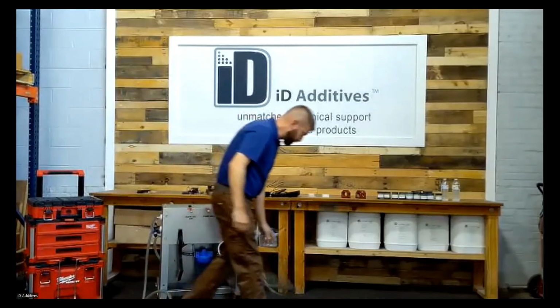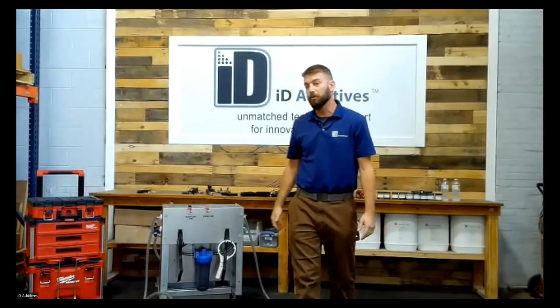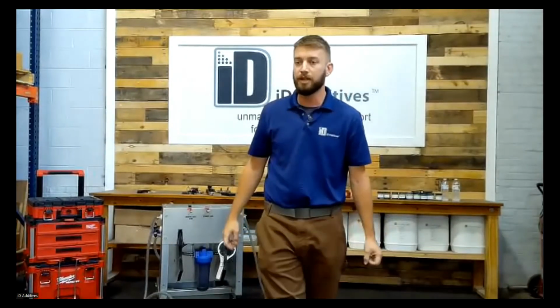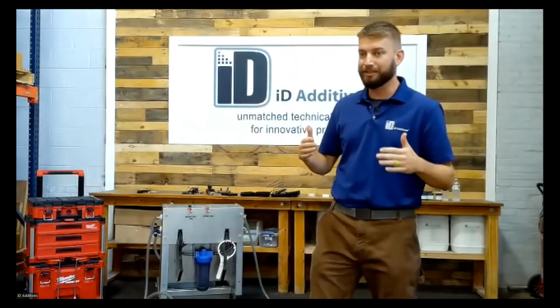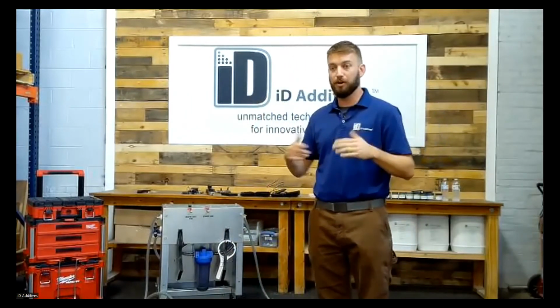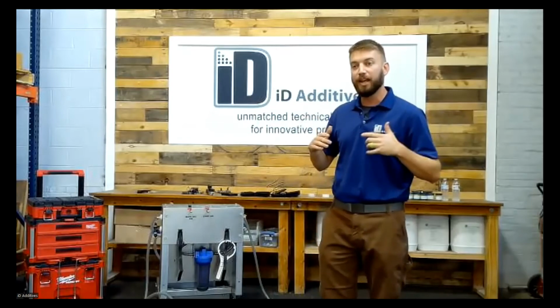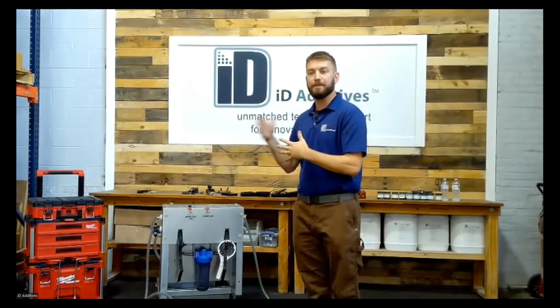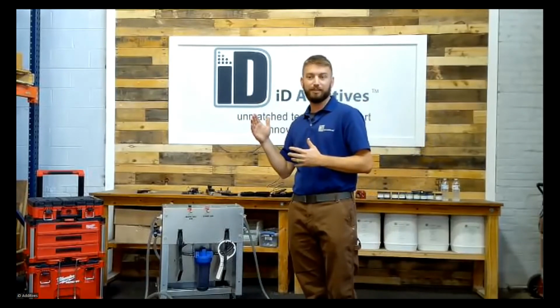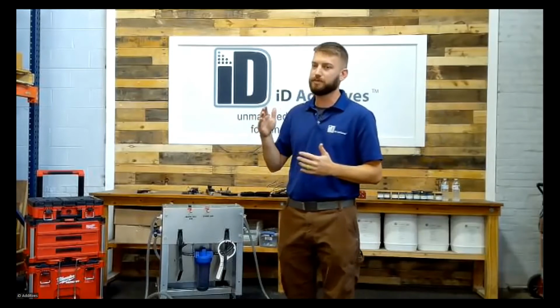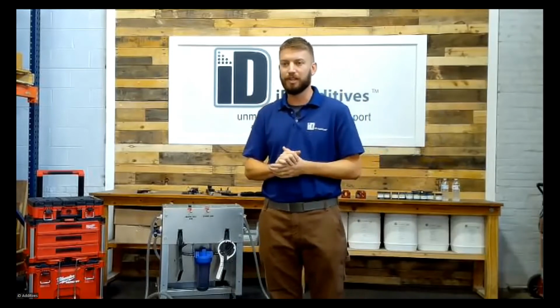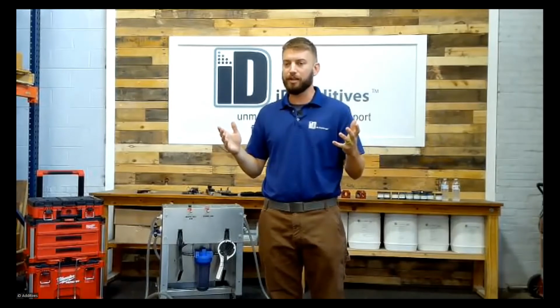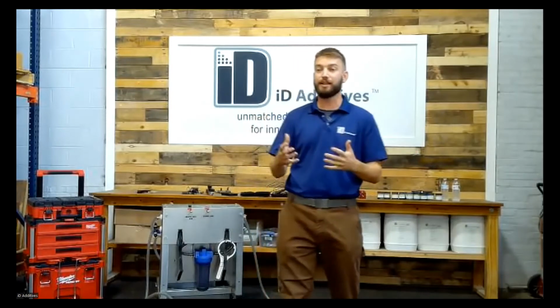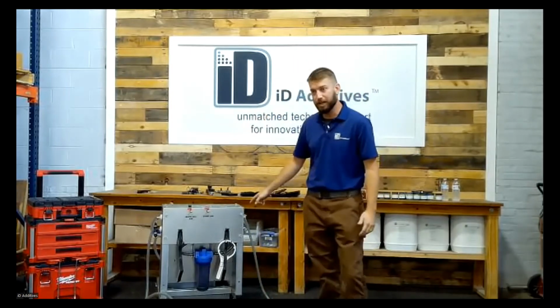So if I go to a facility and we hook up to a mold, which happens quite often, and I'm showing 5 GPMs of flow and everything's cleaning out fine and we're sitting there talking shop, then about an hour later you see those GPMs drop to 4, 4.2, and they'll say, what's going on, your chemical's not working, it's not cleaning out those contaminants. The first thing I check is the filter.